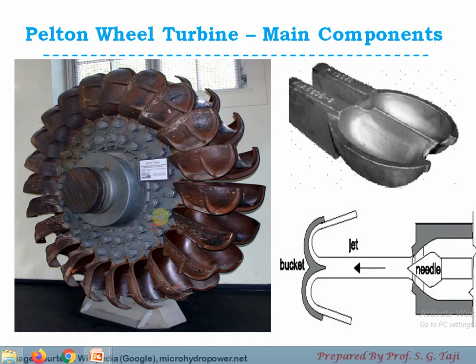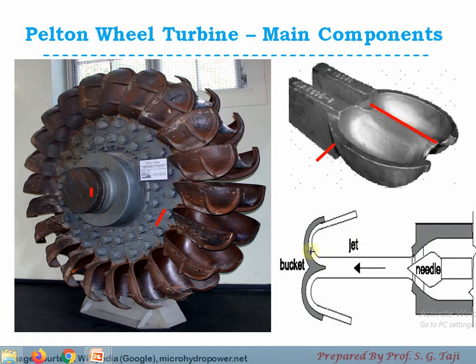The bucket is the most important part of the Pelton wheel turbine. The buckets are bolted on the runner circular wheel, which is coupled with the shaft. Looking at a typical picture of a single bucket, the shape of the bucket is double hemispherical, divided symmetrically into two parts by a ridge line at the center called the splitter. The jet of water strikes on that splitter at the center and gets divided into two halves after striking.